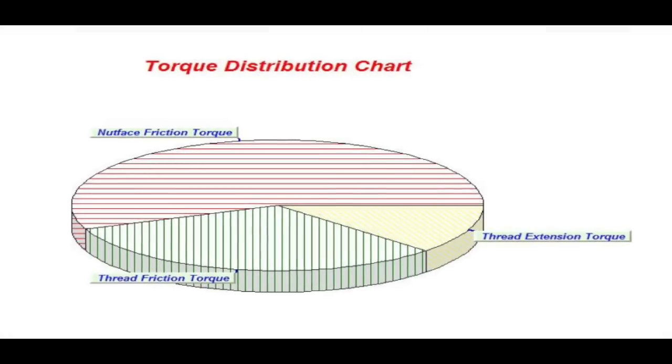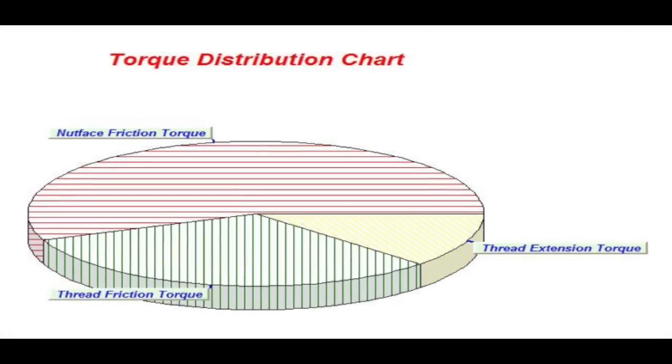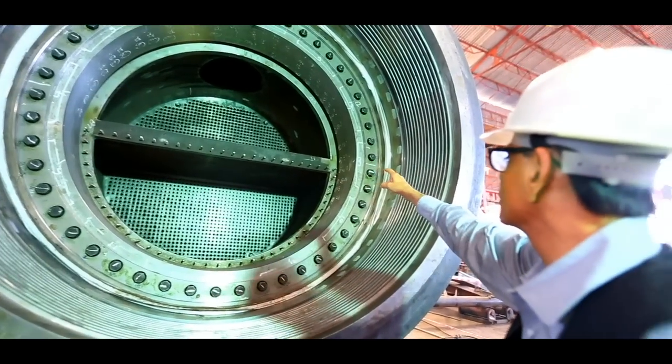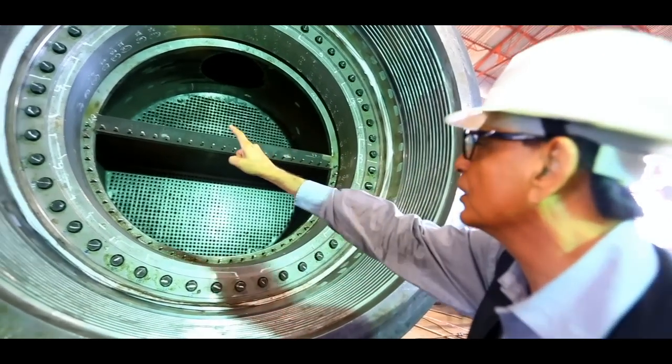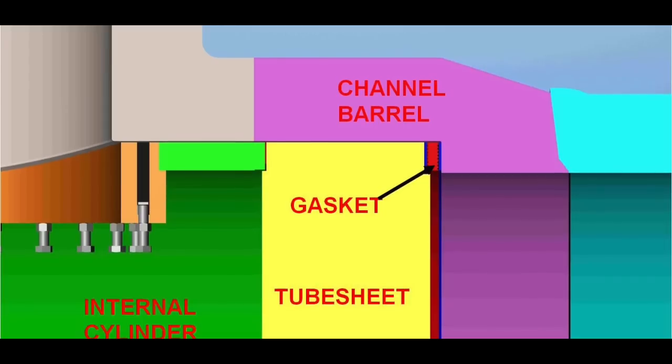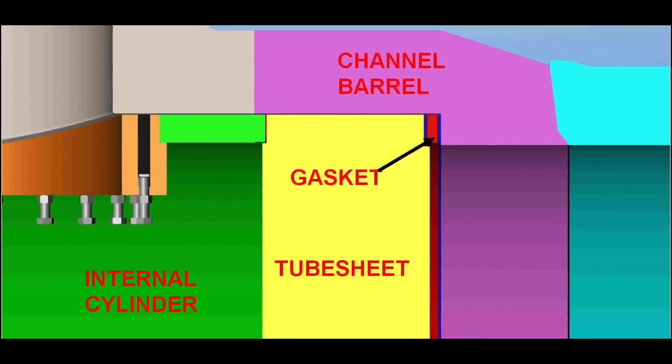We treat torque values as indicative and apply the minimum required initial torque. This is followed by an extensive bolt tightening procedure that measures the compression in the gasket at every single point to give us leak-proof joints conforming to EU standards.